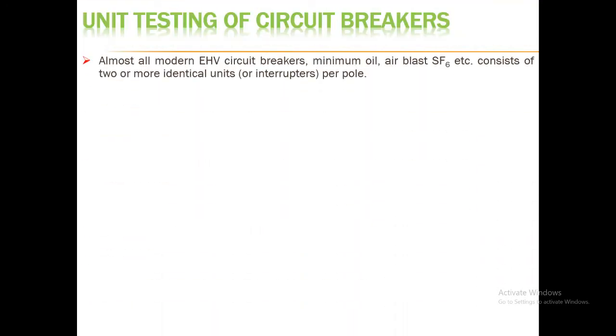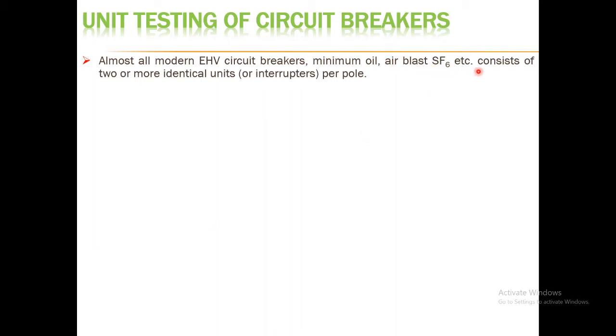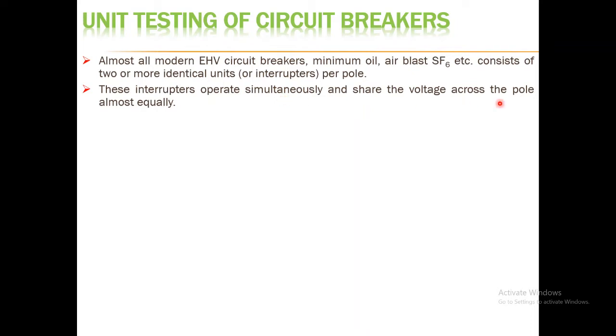Unit testing of a circuit breaker is normally performed on the circuit breaker at the unit level. Almost all modern extra high voltage circuit breakers — minimum oil circuit breakers, air blast circuit breakers, and SF6 circuit breakers — consist of two or more identical units or interrupters per pole. In unit testing, these circuit breakers can be tested by stressing their identical units or interrupters available per pole. These interrupters operate simultaneously and share the voltage across the pole almost equally.